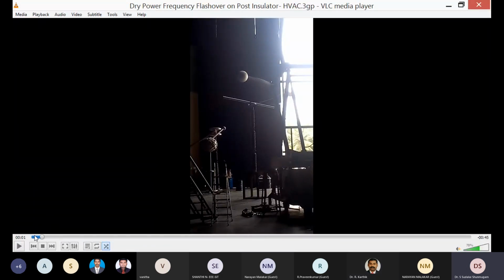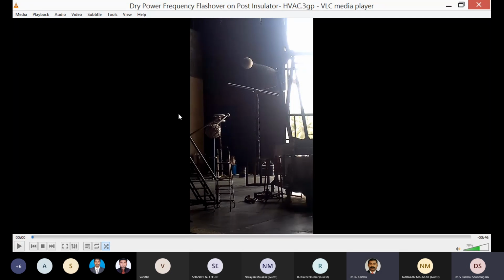What you are seeing is a dry power frequency flashover test on a post insulator. This is the actual testing. We are going to apply a power frequency voltage and keep on increasing it, and we are going to observe up to what power frequency voltage this post insulator, also known as a support insulator, can withstand, and at what voltage flashover happens.